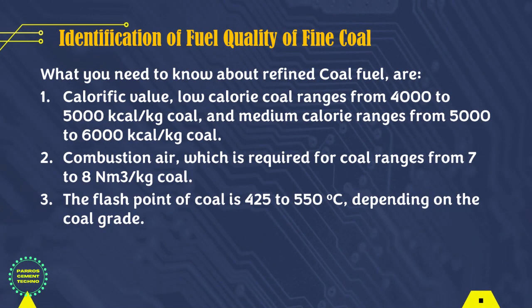For fine coal fuel quality: the calorific value of coal — low calorie ranges from 4,000 to 5,000 kilocalories per kilogram of coal, and medium calorie ranges from 5,000 to 6,000 kilocalories per kilogram of coal. This is important to know, especially when mixing fuel between oil and coal, or changing fuel from oil to coal for the combustion process in the kiln system. Combustion air required for pulverized coal ranges from 7 to 8 normal meter cubic per kilogram of coal, adjusted to fuel consumption. The flash point for coal is from 425 to 550 degrees Celsius, depending on the coal grade.